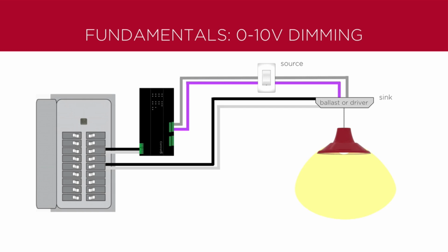However, that naming convention is not always followed by the manufacturers and can affect the number of loads controlled by the module. Sinks usually require 100 milliamps for control. Sources usually require 25 milliamps for control. The standard calls for 0 to 10 volts for control, where the 0 volt command is the minimum on level and each 1 volt increment equals 10% dimming, where 2 volts would be 20%, 3 volts 30%, 5 volts 50% on. However, that standard is not widely adopted nor followed. 3 other standards exist: 1 to 10 volts, 10 to 1, and 10 to 0.